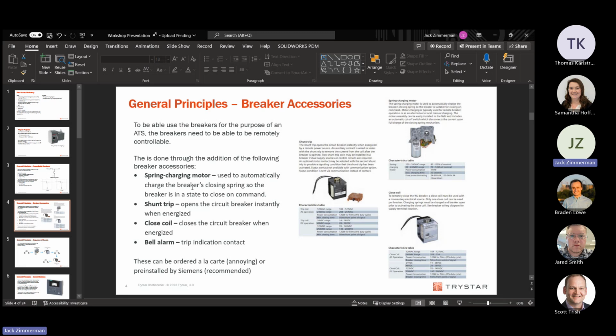And in this case, we do that through breaker accessories. There's 4 main breaker accessories to know for controlling the breakers themselves. And that is the spring charging motor, the shunt trip, the closing coil, and the bell alarm.